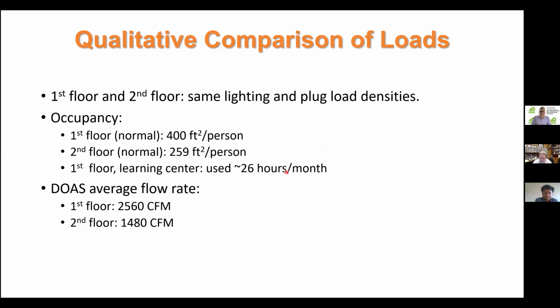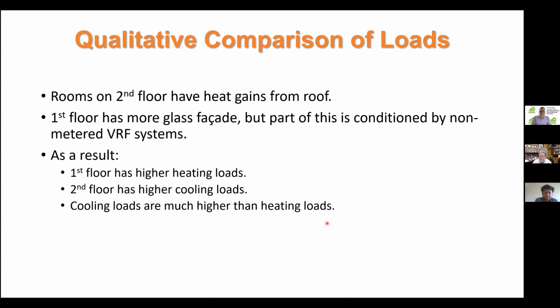But of course, that would increase the load on the VRF system when it was being used, but for a relatively small amount of time. The DOAS system, and I never found the reason for this, provided a bit more flow to the first floor than the second floor. So that would increase the heating load and decrease the cooling load. And the rooms on the second floor have heat gains from the roof. The first floor has some more glass facade, but only some of it is conditioned by the VRF systems that were metered or measured. There was another VRF system that served the entryway, and it wasn't part of the measurement.